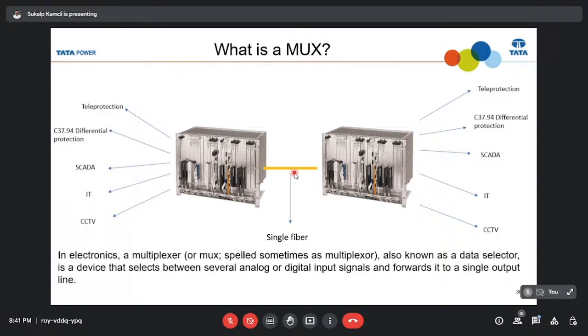Suppose I'm having a single pair of fiber and I want to run multiple applications. You may simply use a multiplexer, or you could use a WDM. But if you're using a WDM, your application interface has to have that specific color wavelength. Applications like teleprotection or this C37.94 protocol and Ethernet don't have wavelengths, so you need that application level inside a device called a multiplexer, wherein multiple applications are handled.